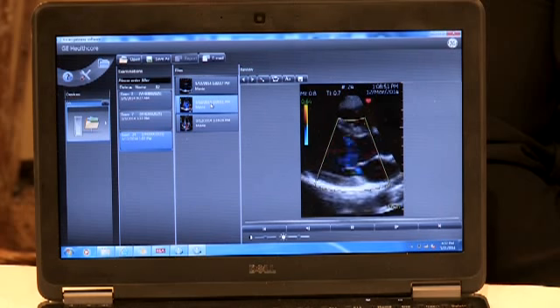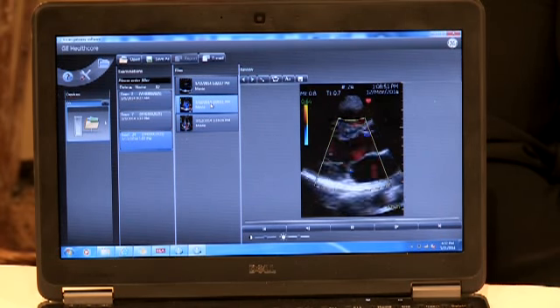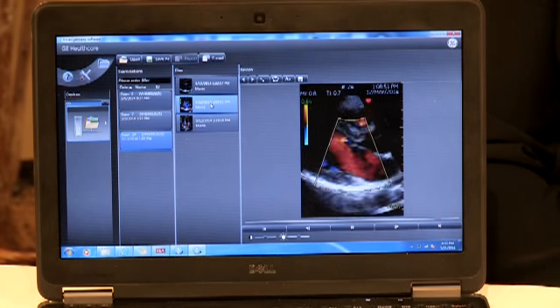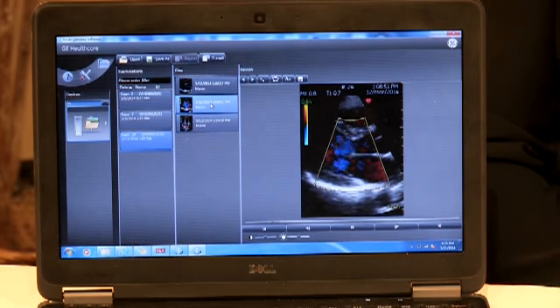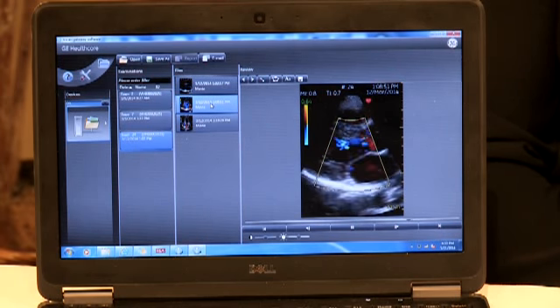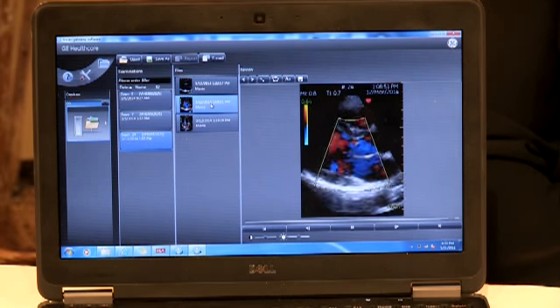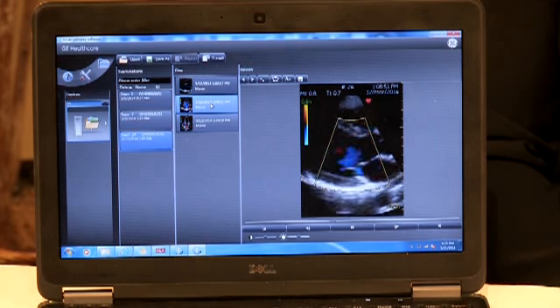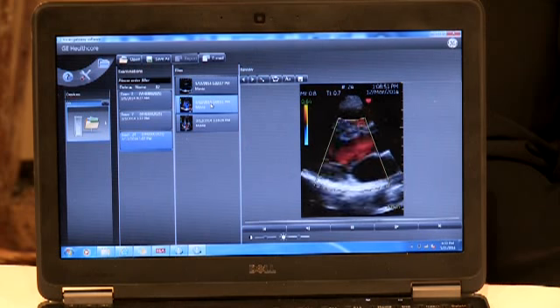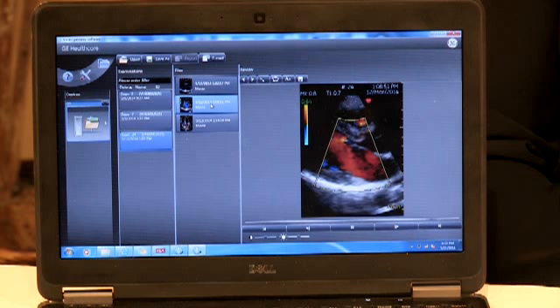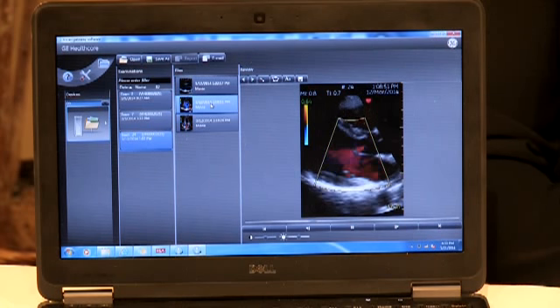The Vscan with dual probe device comes with its own PC software, which provides a gateway between Vscan, customers' PC tools, and GE's service hotline. The gateway is storing Vscan data, which can be viewed and interpreted on the user's PC. This includes basic distance and area measurements. Images with those measurements can be stored back onto the device into the original exam folder. Offline adjustment of contrast and brightness settings are available. And you also have the ability to adjust the patient data, including patient name, ID, birth date, and comments. You have the ability to annotate each clinical image, and there are video controls for the clips, such as play and pause, or back and forward stepping. The Vscan with Gateway can also play back the recorded audio files.